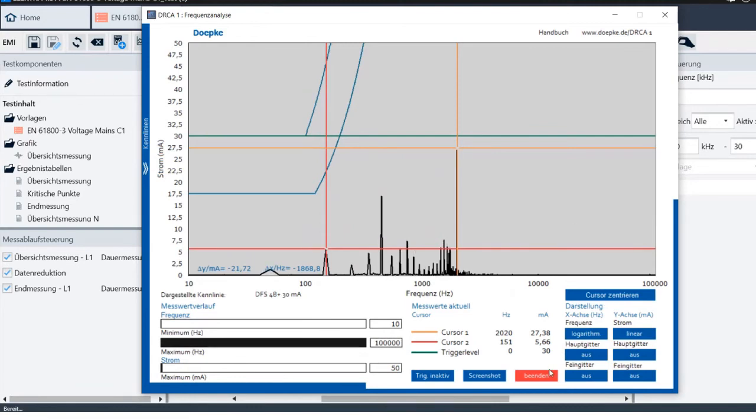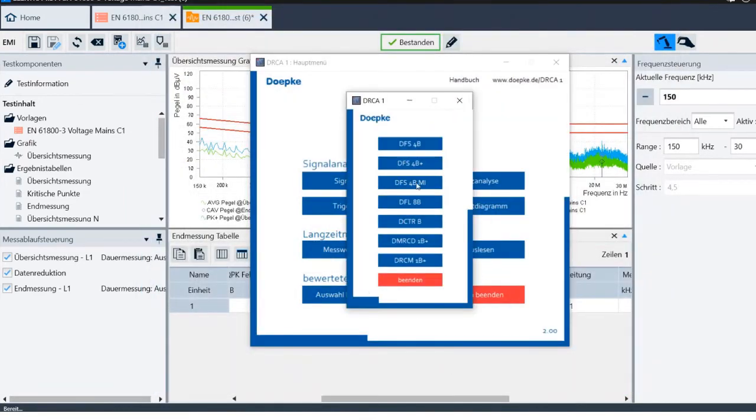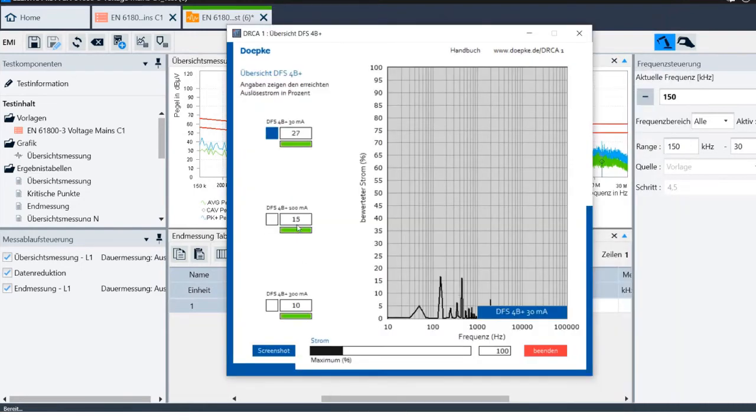And to visualize this even more, there is another function in our system where we can just show, based on the different kinds of RCCBs, which would break or do circuit break. Now you see this here, so we have 25%. This is in percentage. We have 28 or 27% of a 30 milliamp loaded. We have 15% of 100 milliamp and 10% of 300 milliamp RCCB. So there is a lot of space, let's say, to the limits above before we need to change to a bigger one.